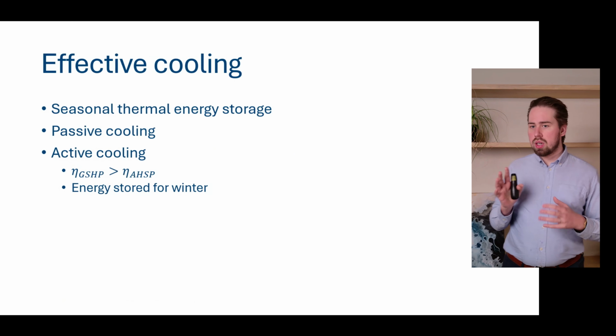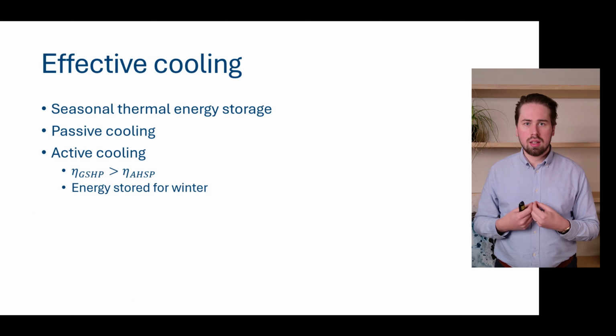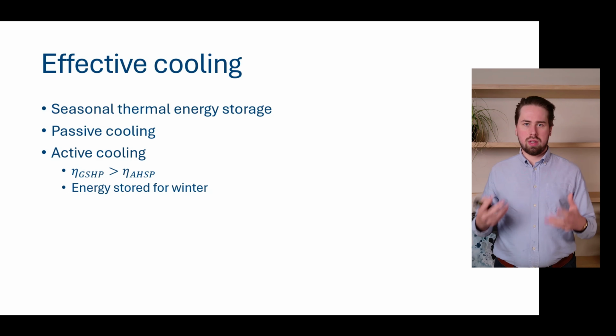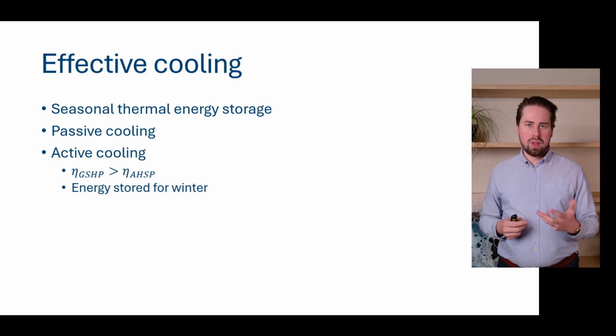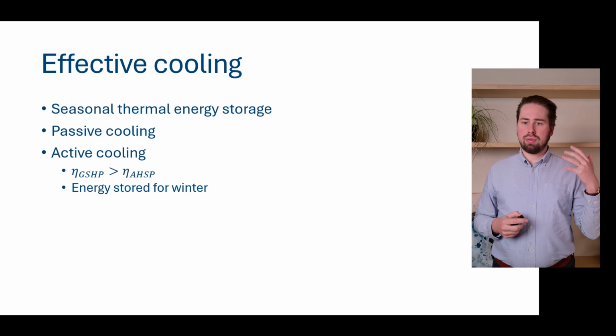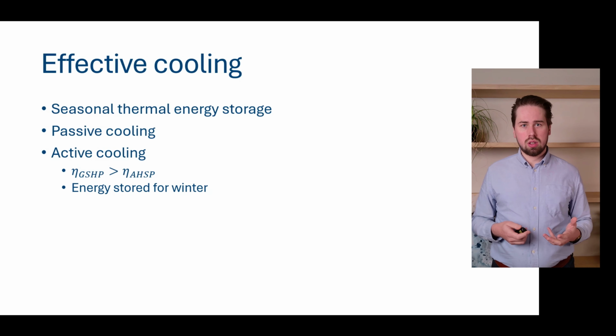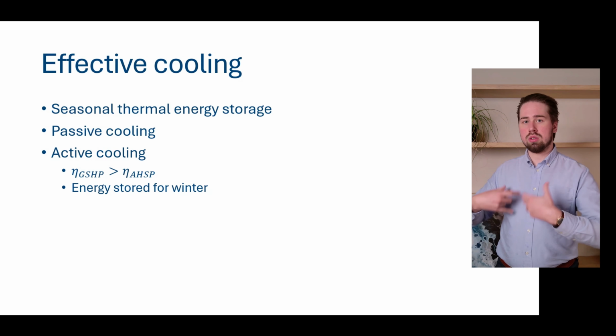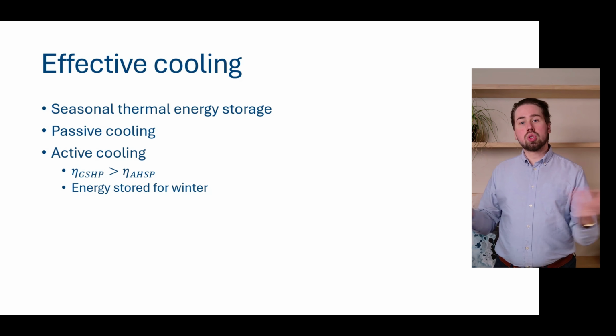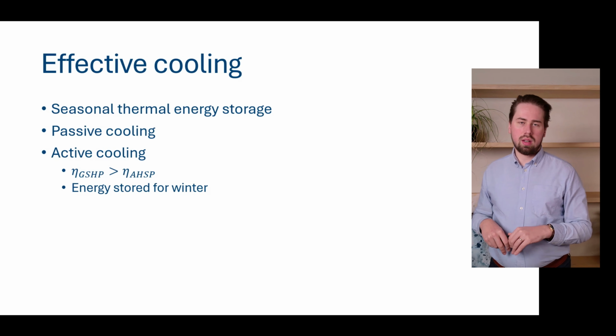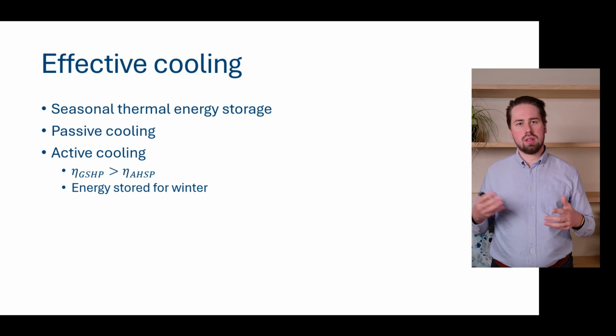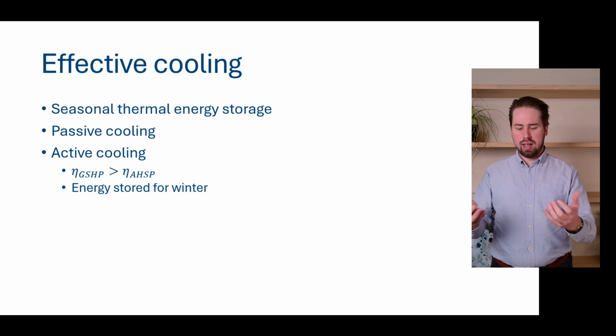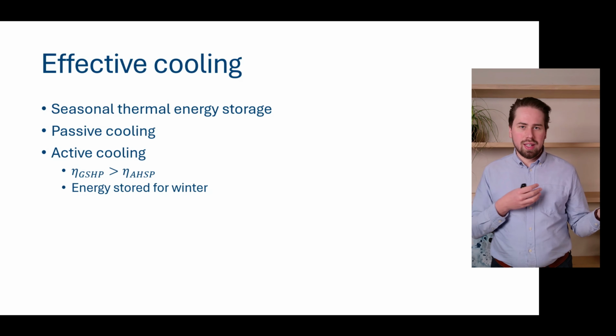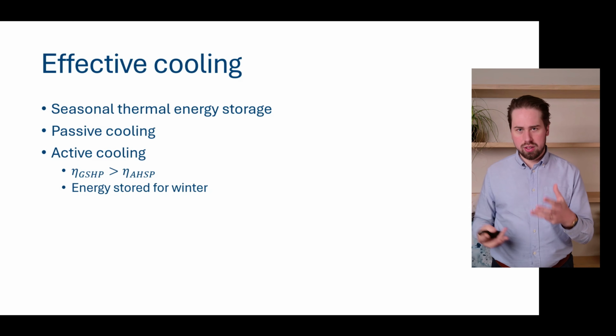Now, when we talk about efficient cooling, ground source heat pumps also have an advantage. We already mentioned the concept of seasonal thermal energy storage, where we're not only taking energy out of the ground, but we can also store it back into the ground. And this is completely different with the outside air. If we take energy out of it, the air cools down. And in summer, the air is gone. There is wind, the air is gone. There is no storage of energy there.